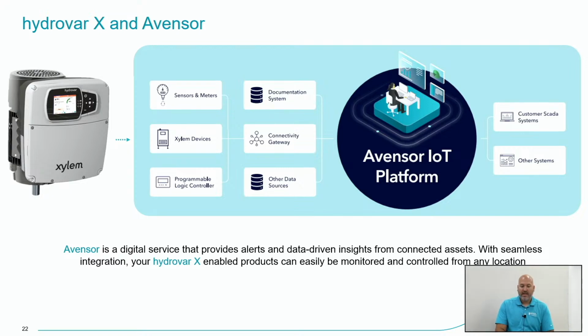So here is Avensor. Avensor is basically its own standalone product. It is a remote monitoring solution. It's a web-based platform, and what it can do is tie into all of our variable frequency drives and give you that remote monitoring capability. You can check the status of your application, the VFD, see if the pump's running, if it's off, if there's alarms. You can do some writing capability or control capability of the product. You can turn it on and off remotely. You can change some pressure set points if you need to.